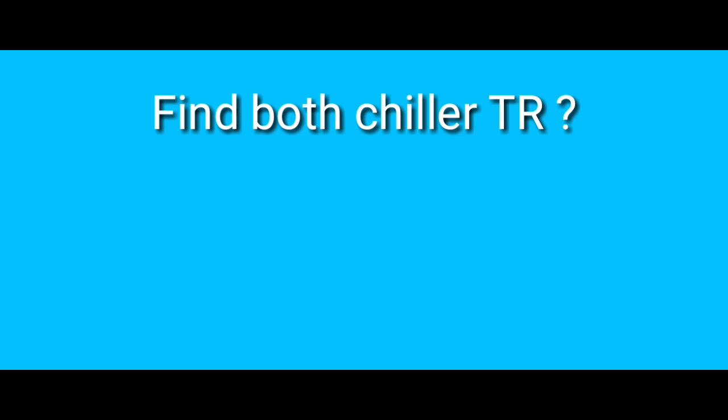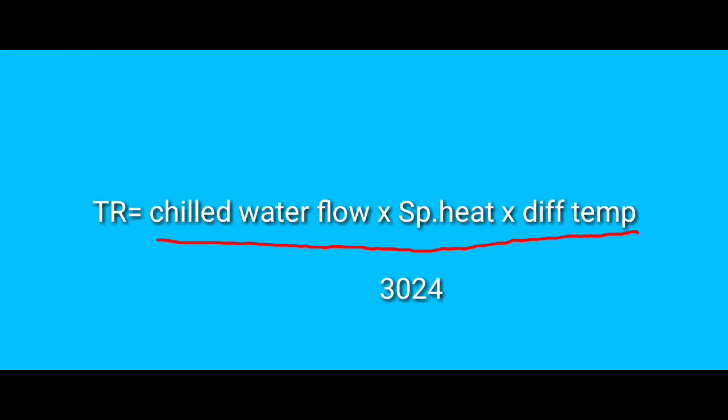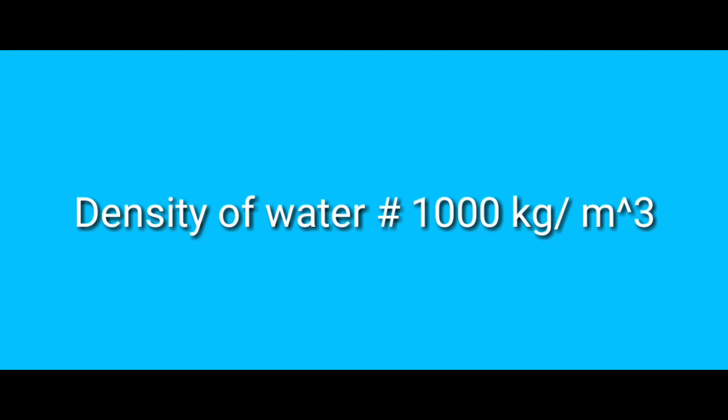So we will talk about auxiliary power and TR value. The TR formula: TR is equal to Chiller Water Flow multiplied by the difference of temperature between inlet and outlet, divided by 3024. Density of water is equal to 1000.